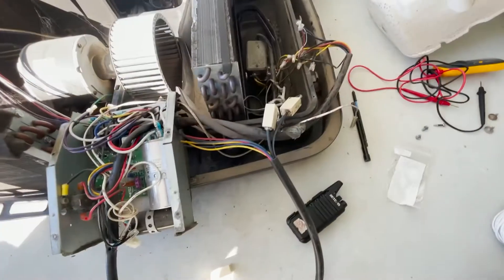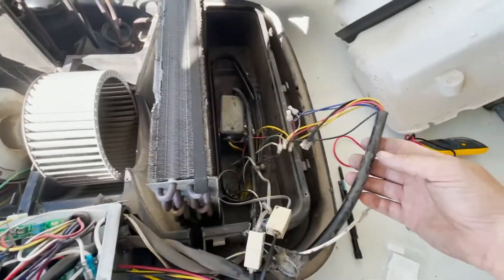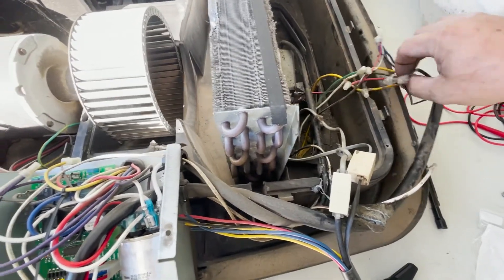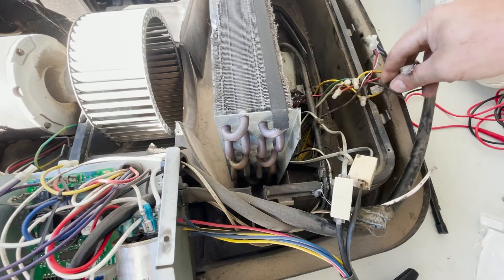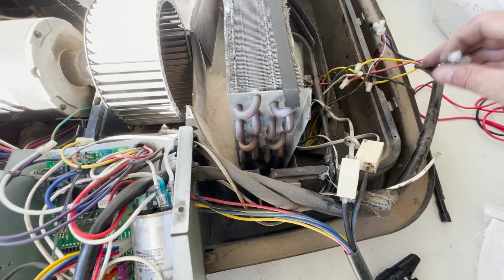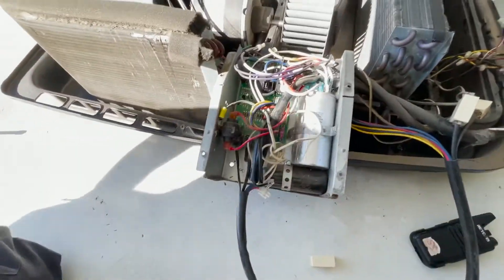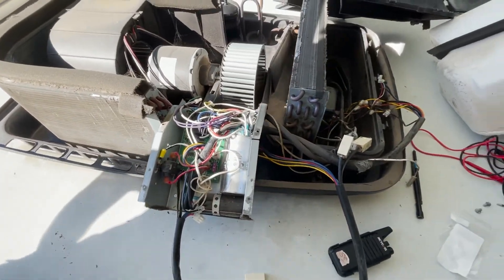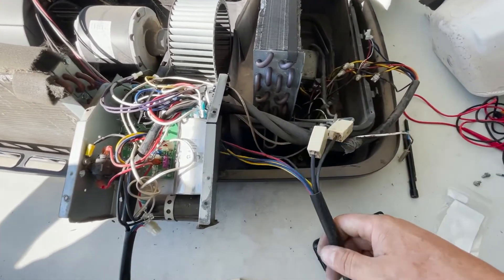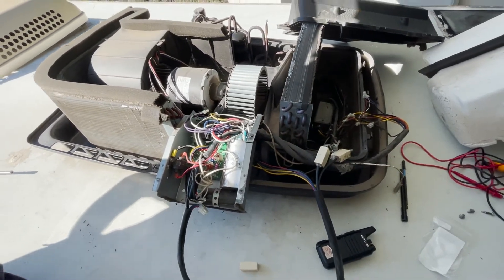After testing, we determined that this cable that supplies furnace control, 12-volt power, and the phone cables that connect here — these cable ends have a problem. Fortunately, I have another one of these plugs, so we're just going to wire it in and be quick. Now that we have communications through the new cable, everything is working great. So Brandon's going to go ahead and change that out, button all this up, and retest — and we should be good.